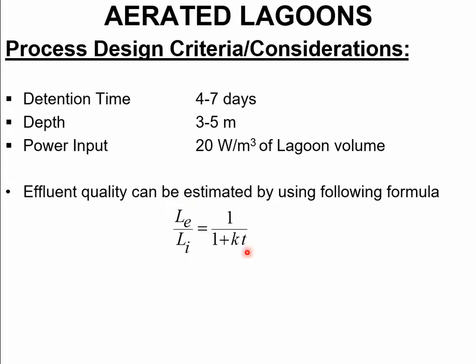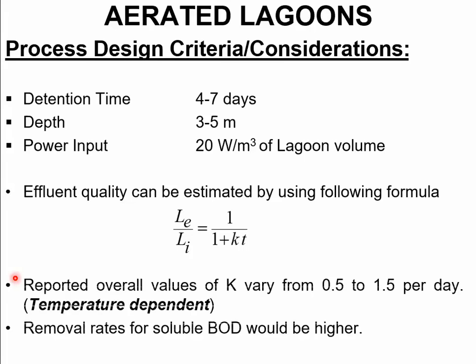depends on the detention time, and K, which is the overall removal rate coefficient or reaction rate coefficient for BOD. The reported overall values of K vary from 0.5 to 1.5 per day, and removal rates for soluble BOD would be higher. Soluble BOD is quite easy to oxidize by bacteria, therefore its removal rate or K value would be higher.